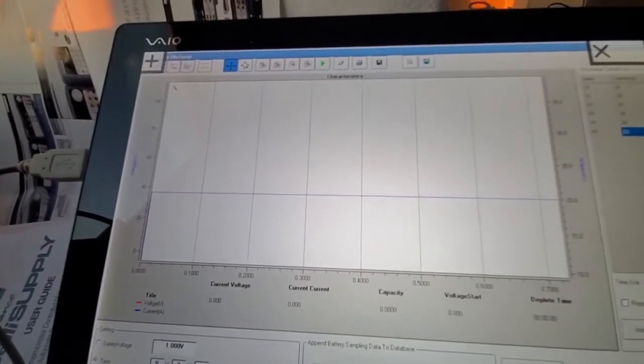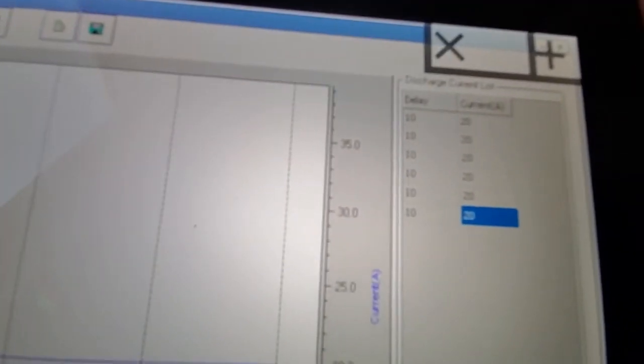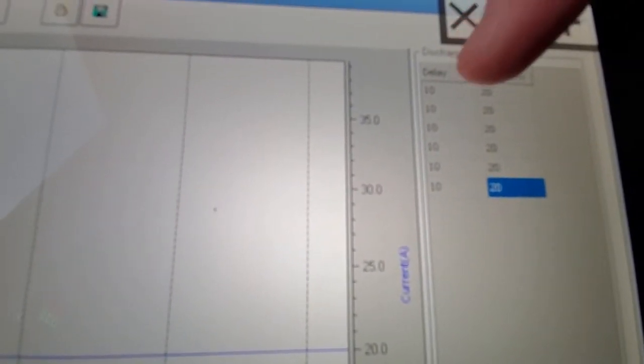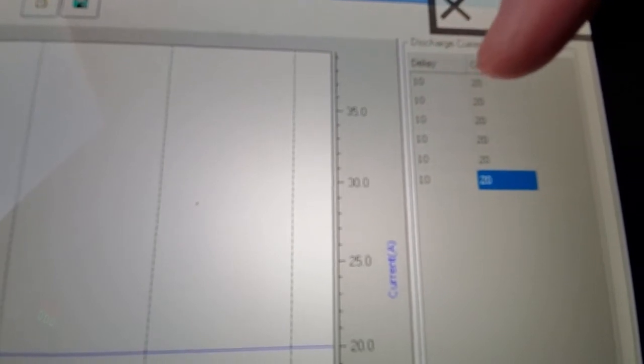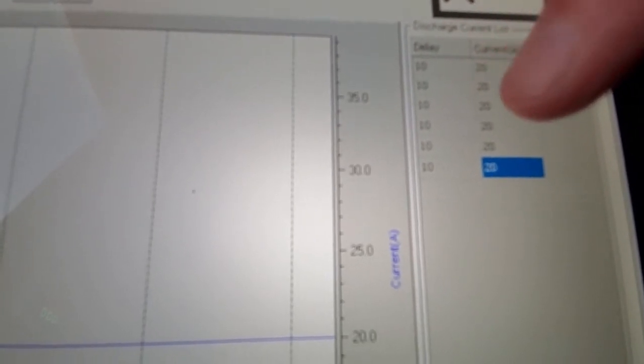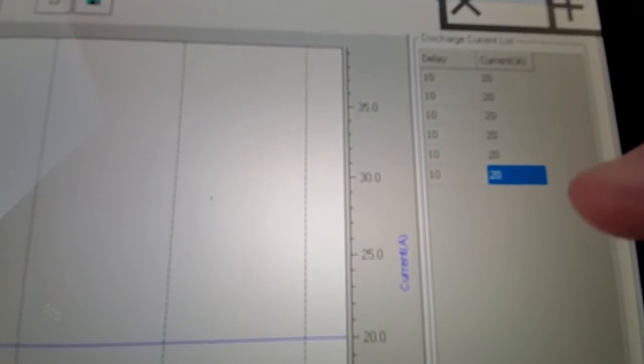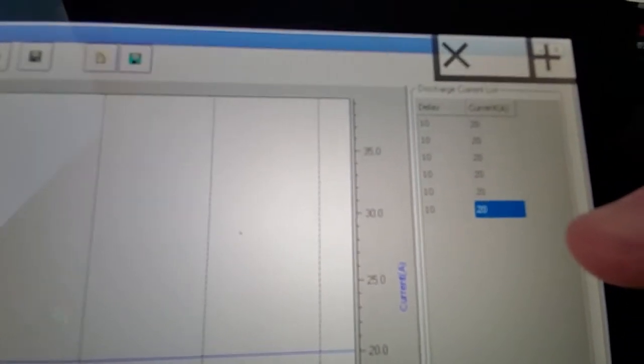So now it's ready to record, and I've set it up over here to do 10 seconds at 20 amps, and they're all the same. So I'm doing—then it'll run all of these down till it gets to the very bottom one.